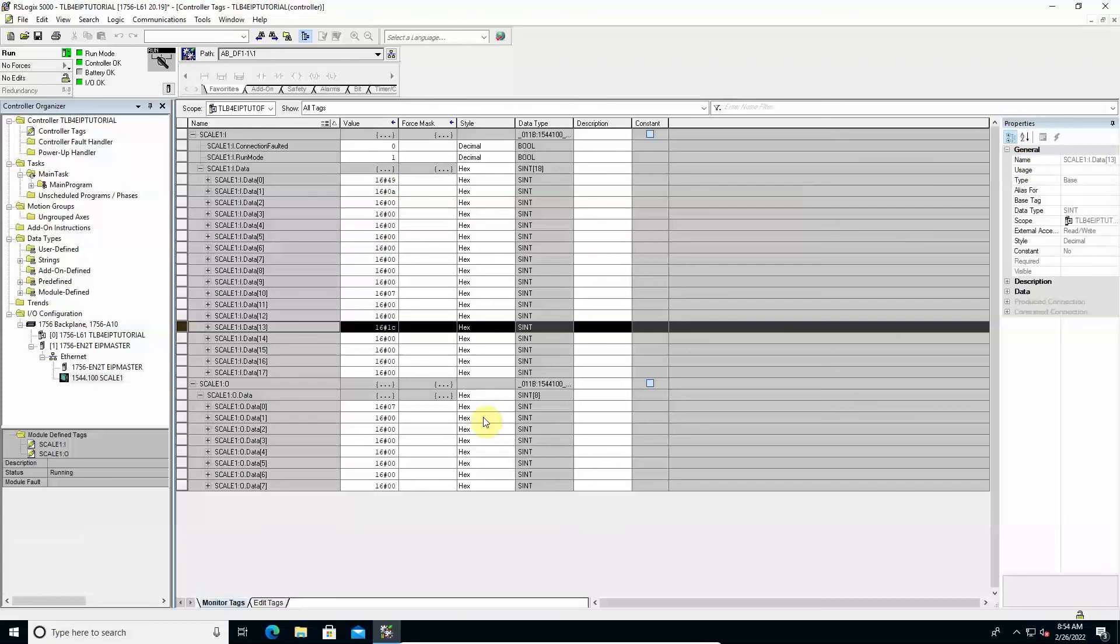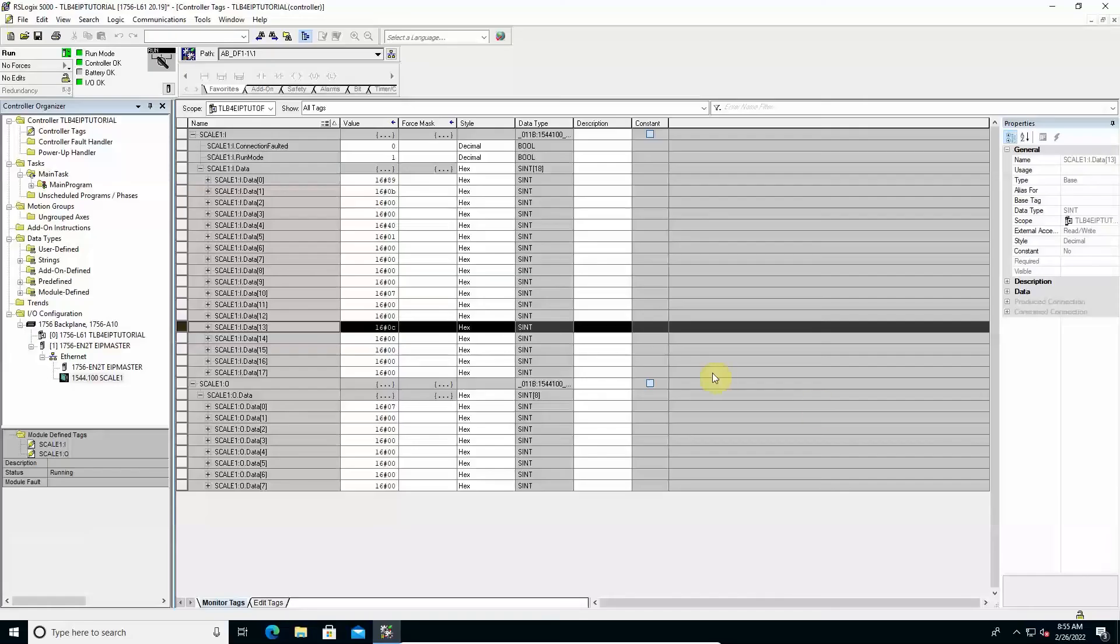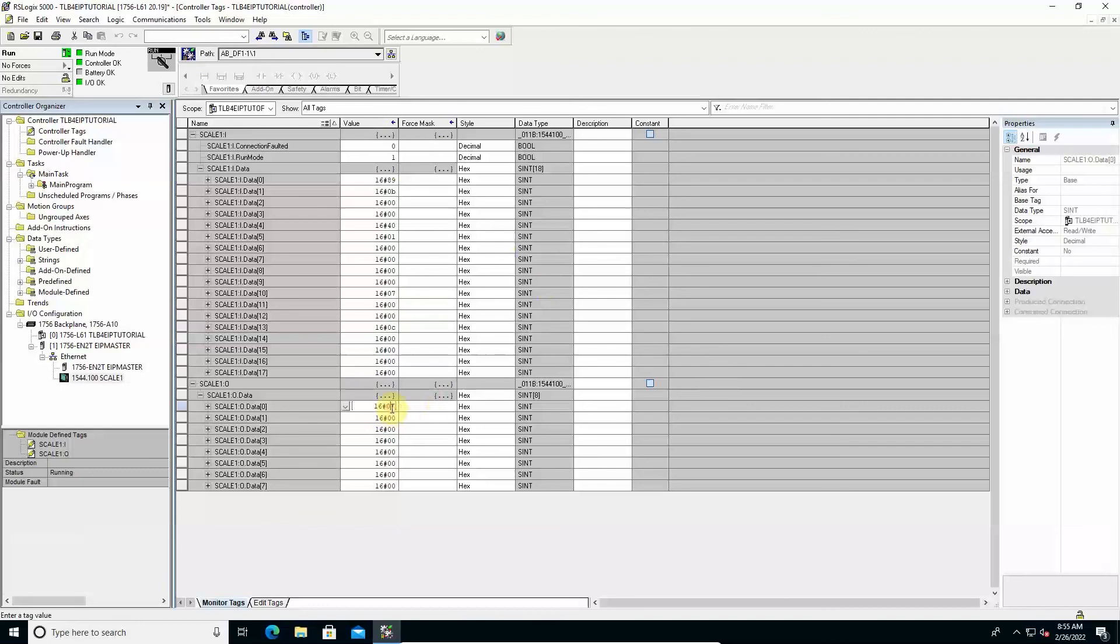To repeat the same operation several times, it is necessary to interpose the writing of the value 0 in the command register to the writing of the numerical code corresponding to the operation. For example, applying this sequence, we can perform a second semi-automatic tare after applying an additional weight to the scale.